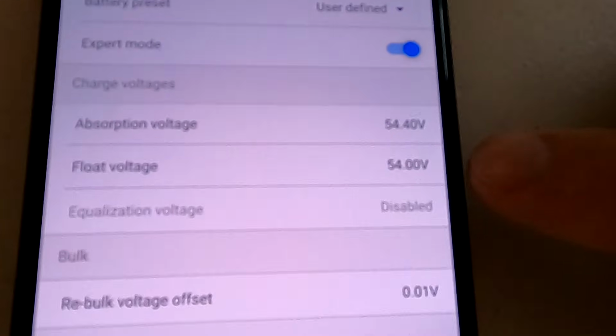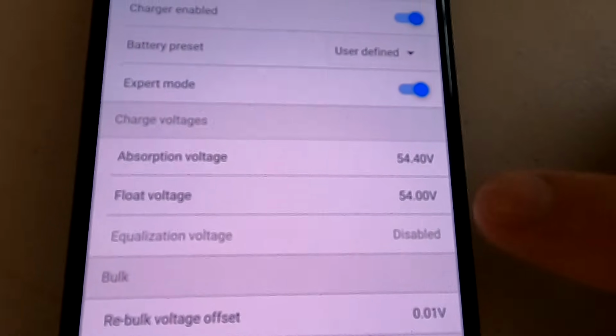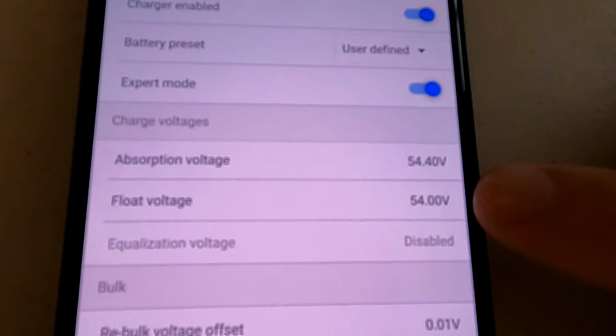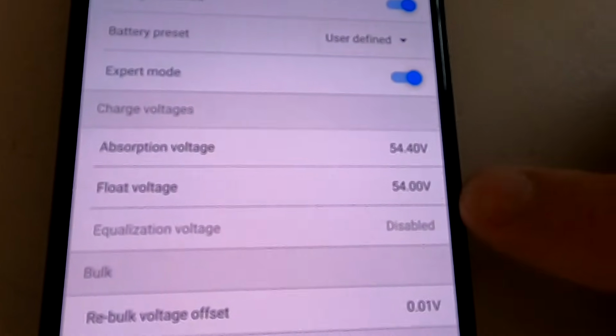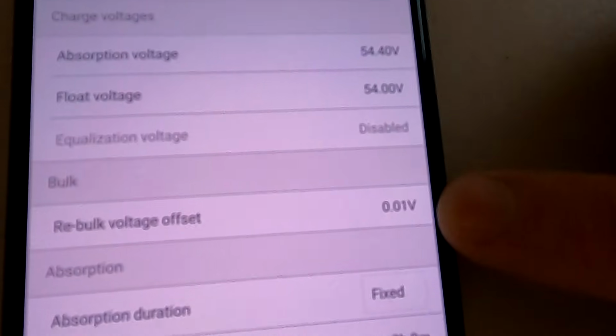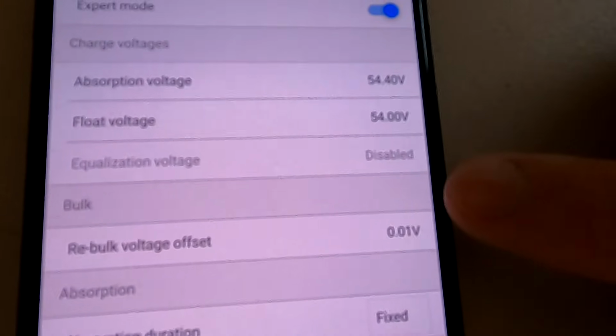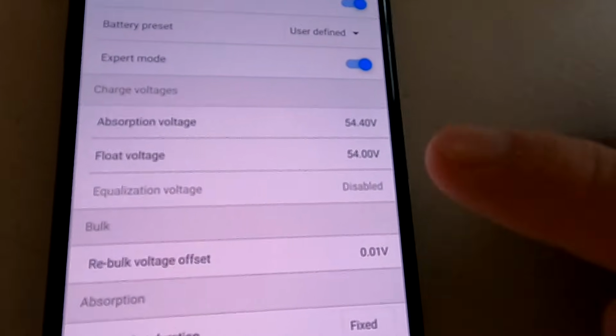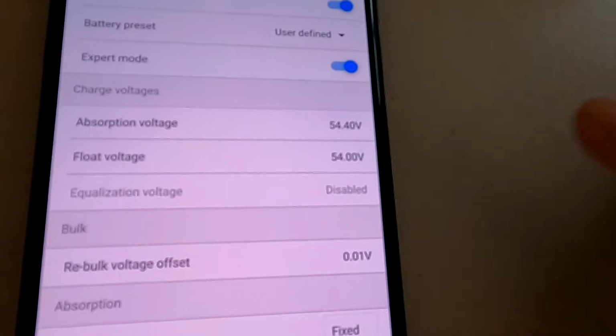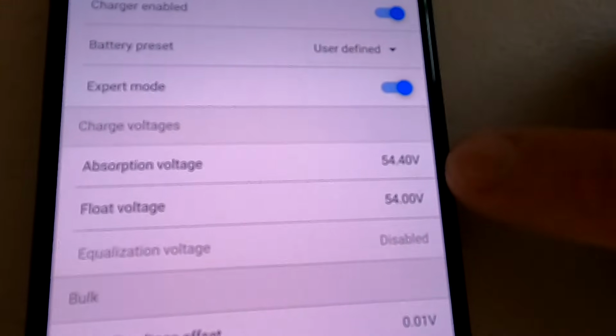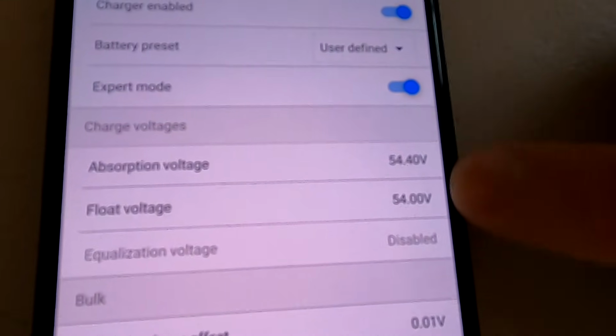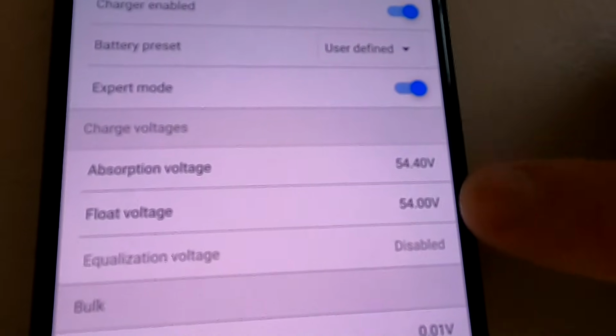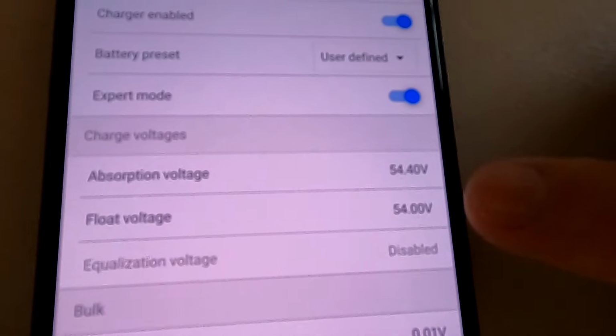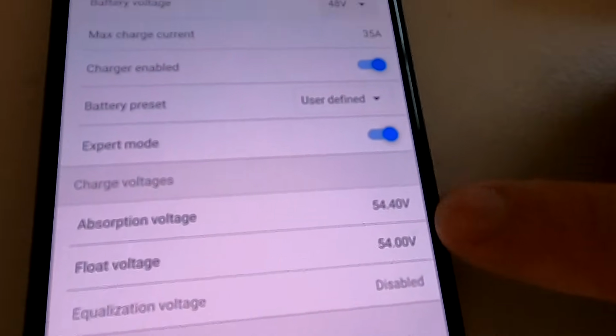Float mode is 54, so it will wait until the battery reaches 54 volts. If it goes 10 millivolts under this 54, it will recontinue and start a new cycle with bulk, absorption, and float. But in between these two figures, there's nothing happening from solar - solar will be totally off. This is what I'm trying to minimize.